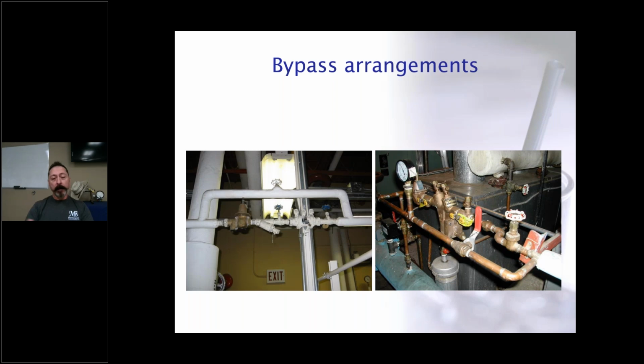One of them is that you cannot have a bypass arrangement around a backflow preventer. I inspect a lot of facilities, and I see this very commonly. It's an installation nightmare that we're seeing these bypasses installed, and you can't have that because the contaminant can back pressure or back siphon right around the whole backflow preventer. And a shutoff is not considered a means of isolation according to any standard or any backflow manual. So the shutoff valve doesn't count.